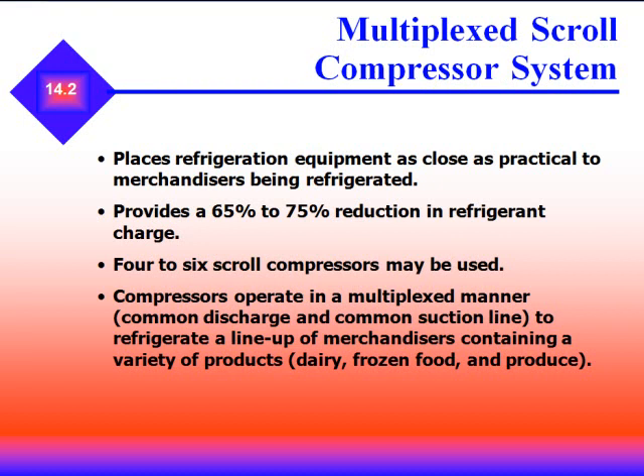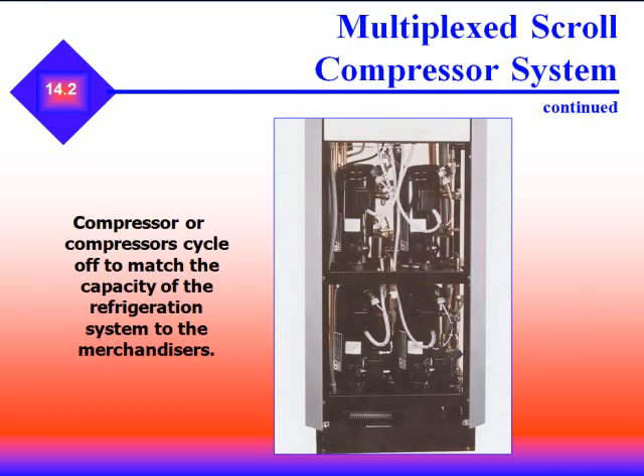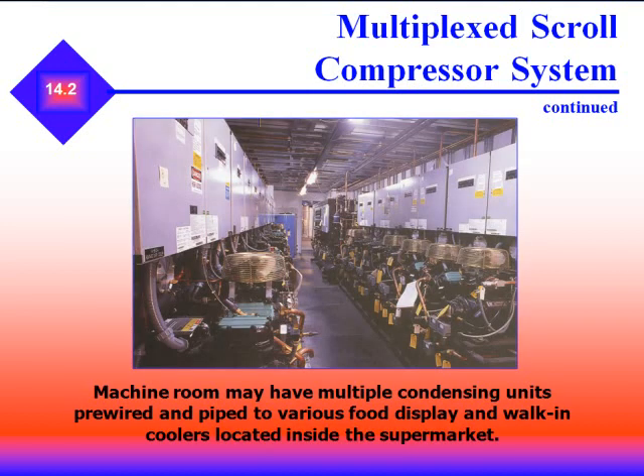Multiplexed scroll compressor systems place refrigeration equipment as close as practical to the merchandisers being refrigerated, providing a 65–75% reduction in refrigerant charge. Four to six scroll compressors are used, operated in a multiplex manner with common discharge and common suction lines to refrigerate a lineup of merchandisers containing a variety of products — dairy, frozen food, produce. Machine rooms may have multiple condensing units pre-wired and piped to various food display and walk-in coolers located inside a supermarket.